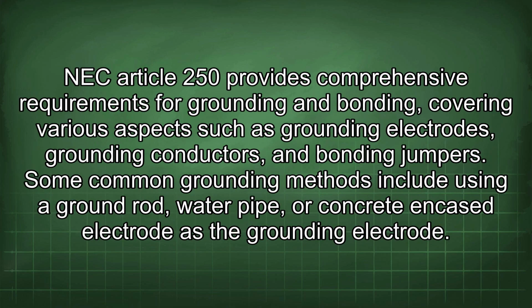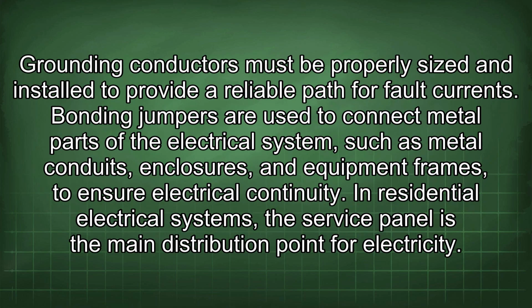of shock. NEC Article 250 provides comprehensive requirements for grounding and bonding, covering various aspects such as grounding electrodes, grounding conductors, and bonding jumpers. Some common grounding methods include using a ground rod, water pipe, or concrete encased electrode as the grounding electrode. Grounding conductors must be properly sized and installed to provide a reliable path for fault currents.